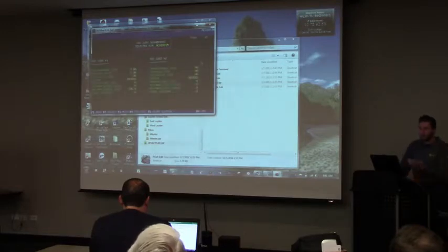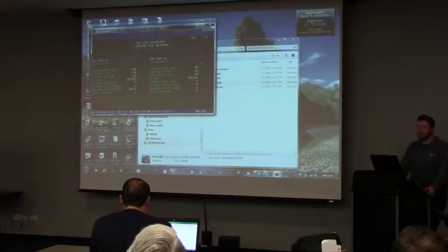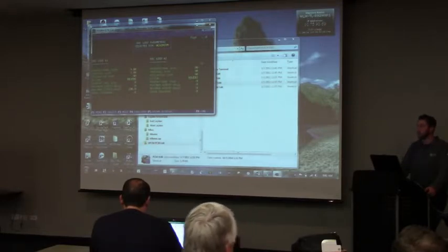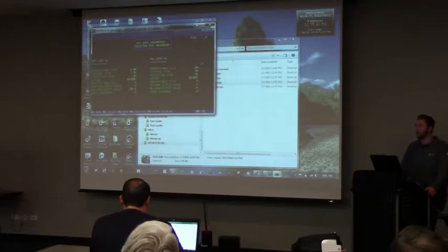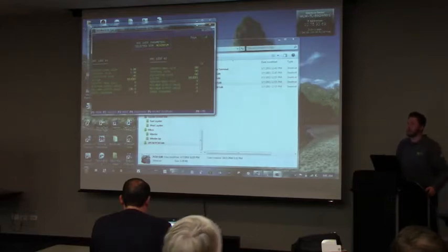But right here, you have your proportional gains, integral gains, action, reverse, pretty much everything on a PID loop, but they call it a DDC loop in the PCMs and UPCMs. Same principle, 4-to-1 ratio is what they have it set up for. And the same thing with your action with reverse or direct. So then you have your min and max and all that kind of stuff. Then you have your dead band too. So very, very similar to a PID loop if you guys are trying to use that in a PCM or UPCM.